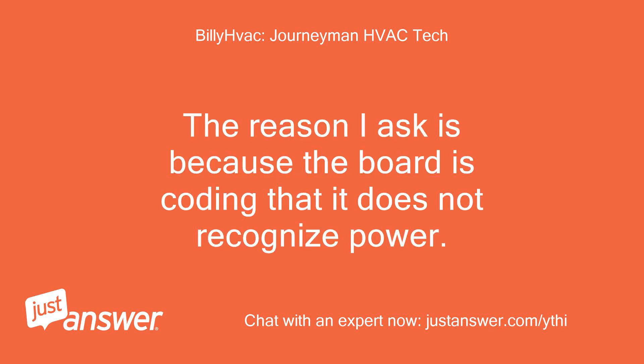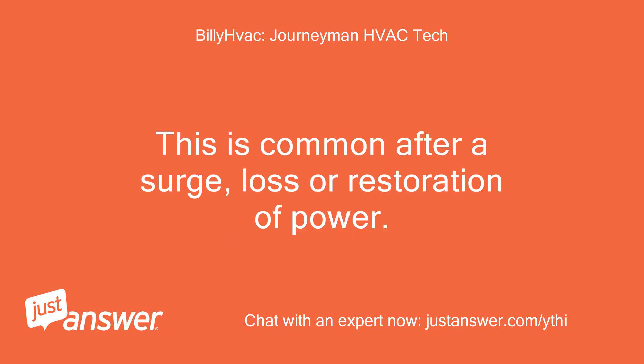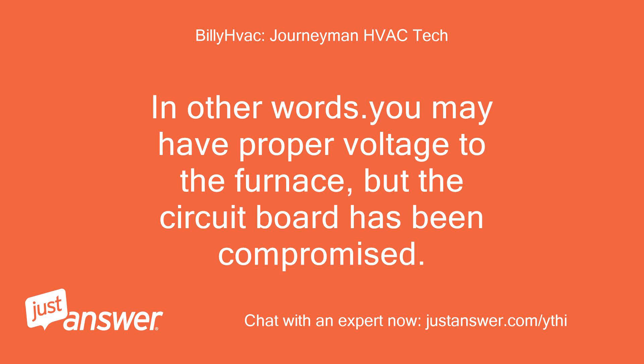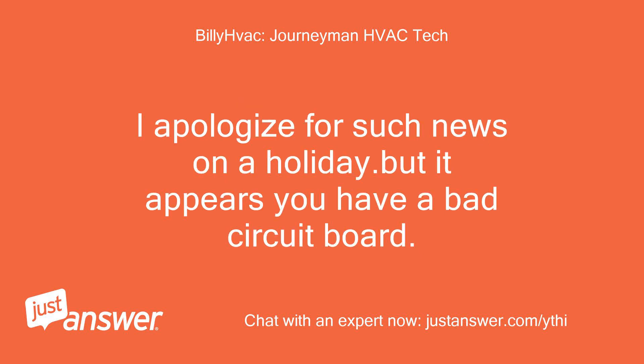The reason I ask is because the board is coding that it does not recognize power. This is common after a surge, loss, or restoration of power. In other words, you may have proper voltage to the furnace, but the circuit board has been compromised. I apologize for such news on a holiday, but it appears you have a bad circuit board.